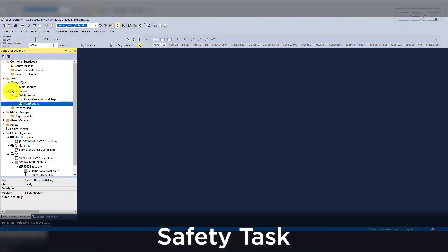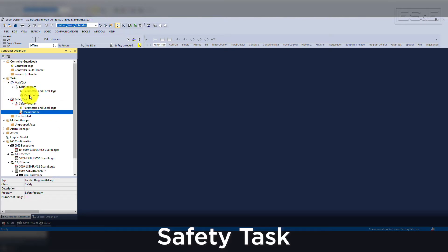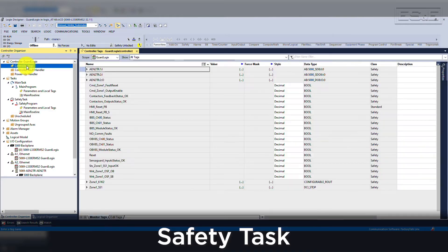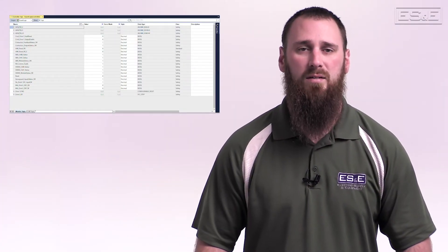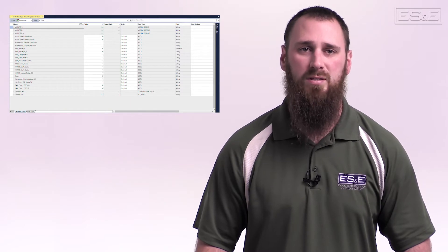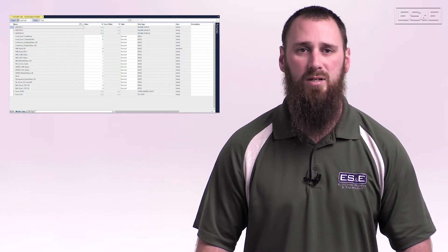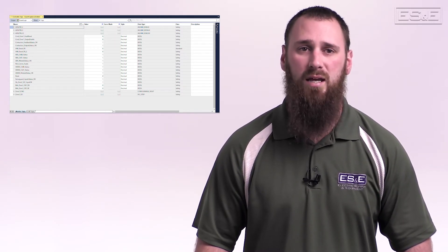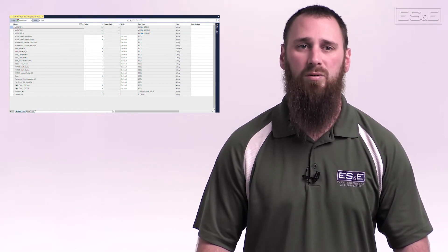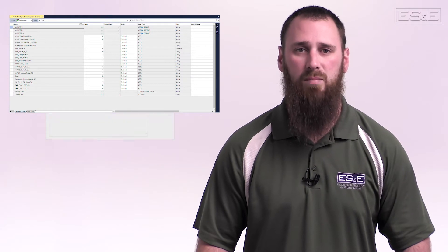Outside of the safety task, you will have your standard logic, and the standard logic can reference any of the safety tags, but it only works as a read function and cannot be destructive. The safety task takes a snapshot of the safety inputs prior to scanning the logic, so if you need to get data from the standard task into the safety task, you will need to create a safety tag map.